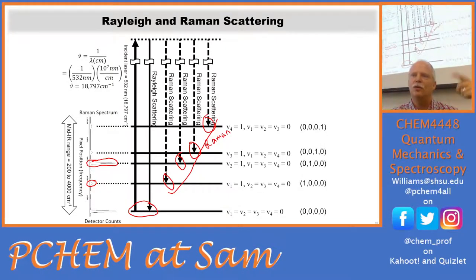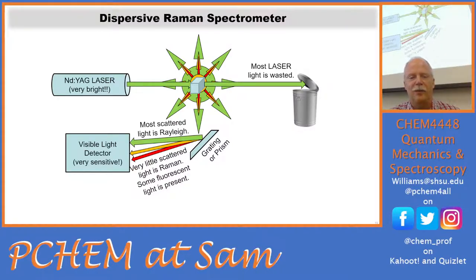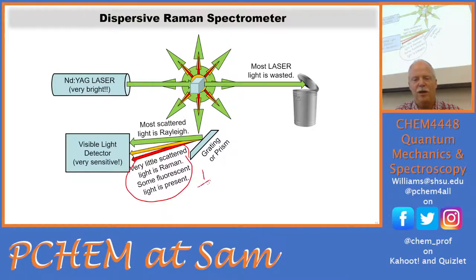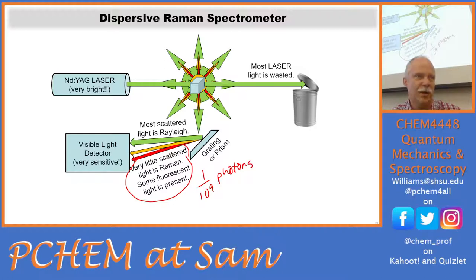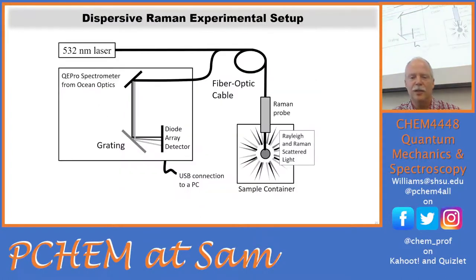We detect red-shifted Raman photons at particular frequencies corresponding to the fundamentals, and those spectra line up with infrared. Most laser light is Rayleigh scattered or passes through — we have to throw that away and look at the Raman-scattered light, which is only about one in a billion photons. Without a laser this wouldn't be a practical technique — lasers provide so much light in a particular direction.